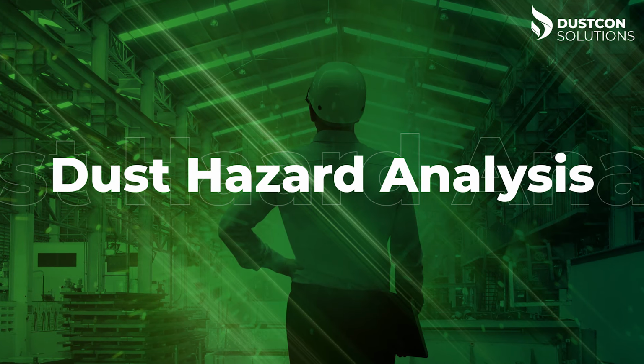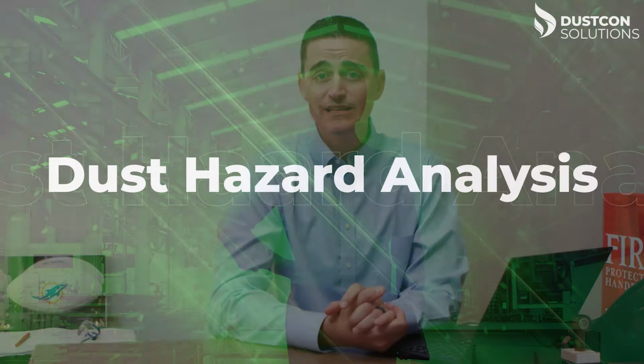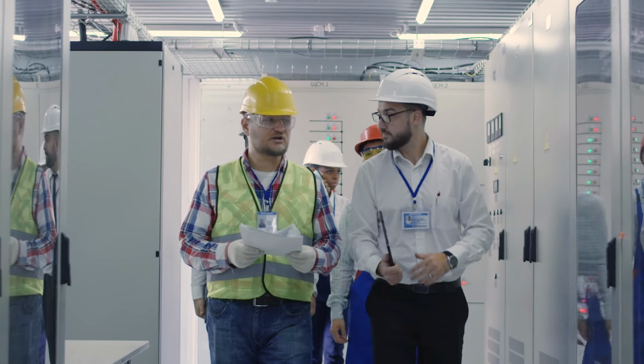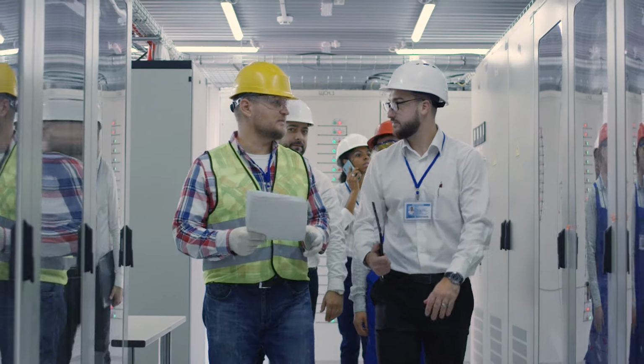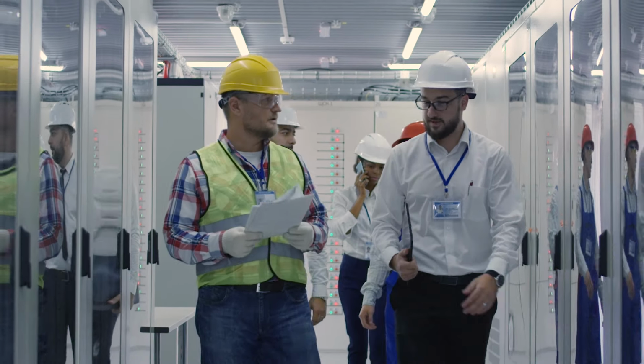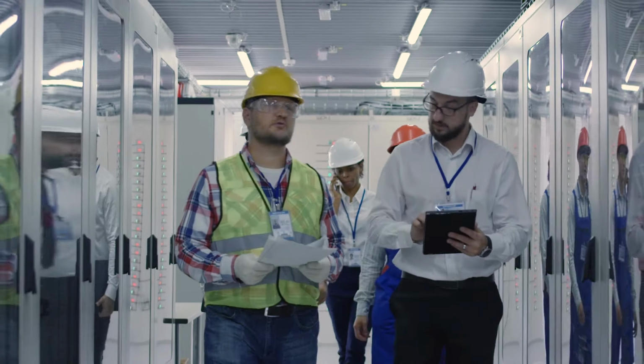A dust hazard analysis, sometimes called a DHA, is a requirement of the NFPA standards related to combustible dust. It is a thorough assessment of the hazards, existing safeguards, and any gaps that may need to be filled within your process or your facility to ensure safety for your employees and continued operation of your business.